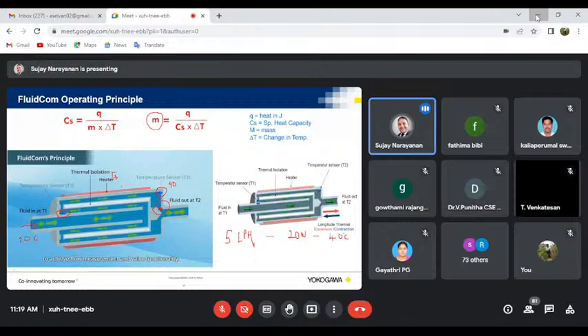It will see whether 10 liters per hour is achieved, and then it will try to close or open the control valve, like a PID algorithm is there within, and it will keep the proper orifice. So in this way, it is able to measure the flow rate, and also by simultaneously controlling the orifice of the opening, it is able to control the flow rate. That's why I say it has the heater, the flow measurement, control valve, actuator, and the PID algorithm all in one device. So this is how this particular device works.